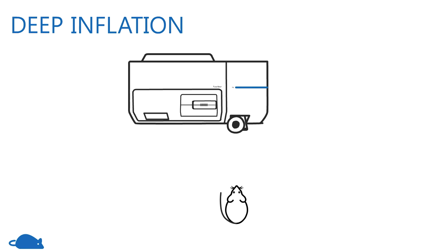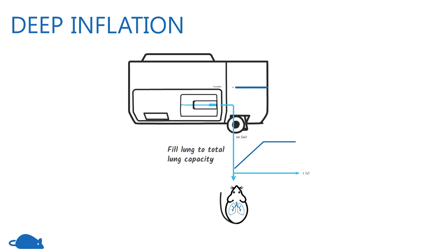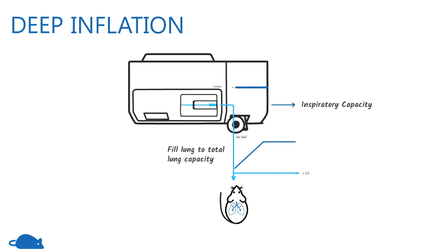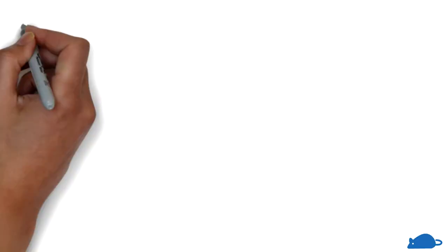In the deep inflation measurement, the lungs are recruited to total lung capacity, followed by a brief hold for lung pressure equilibration. The inspiratory capacity is calculated as the total volume change due to the measurement.